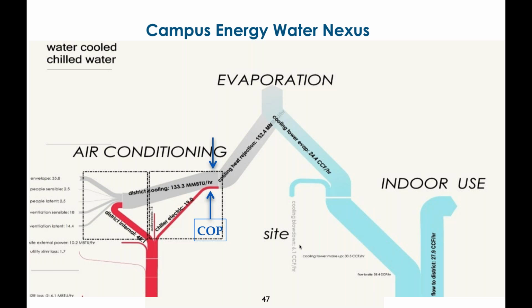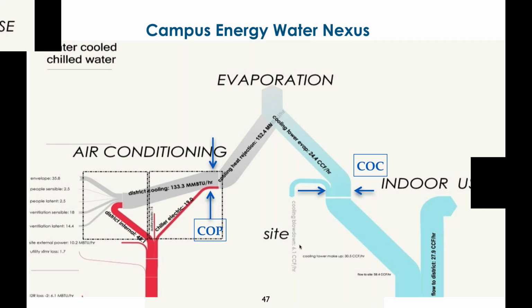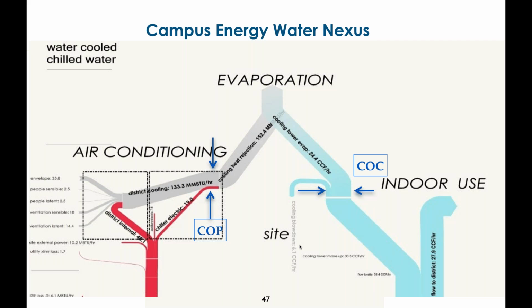Two key parameters here: the coefficient of performance, how efficient your chiller plant is, gives an idea of the ratio of electric energy needed to pull the heat out. On the water side, the cycles of concentration is the ratio of water you're blowing down to keep the chillers efficient. There's a close coupling between energy efficiency and cooling tower water use: the less energy you're extracting from campus, the more efficient your buildings and distribution system and plant, the less water you have to pull out.